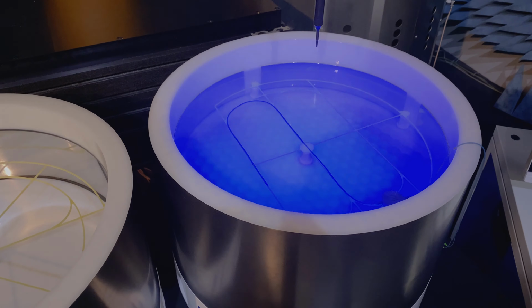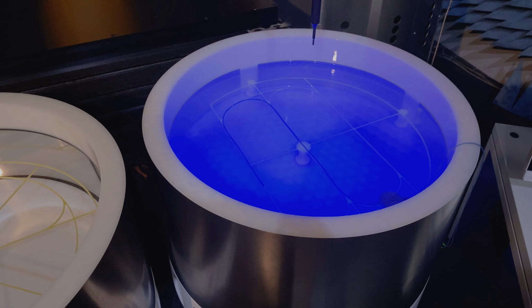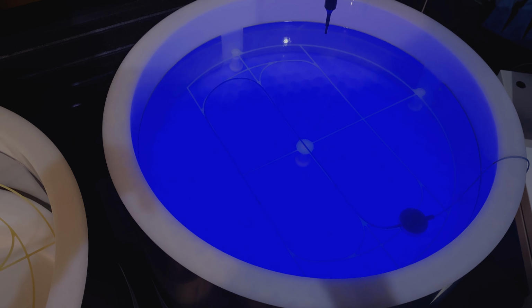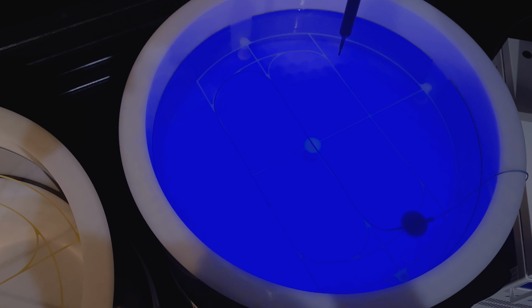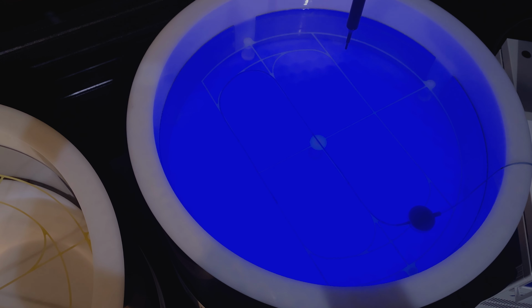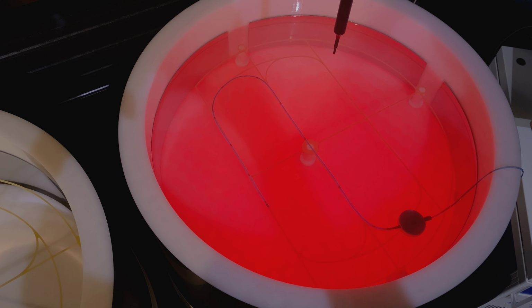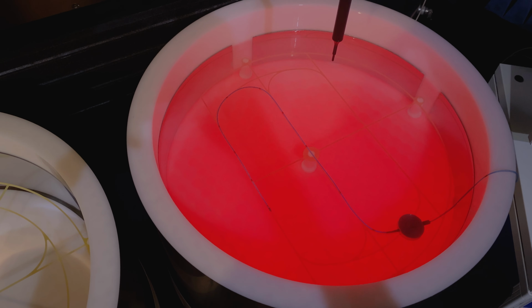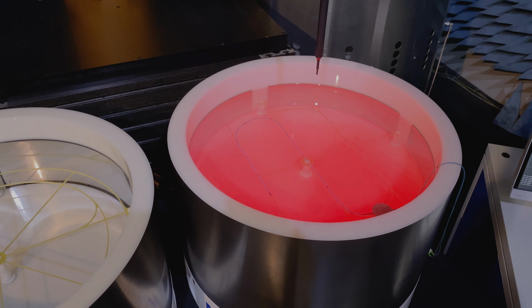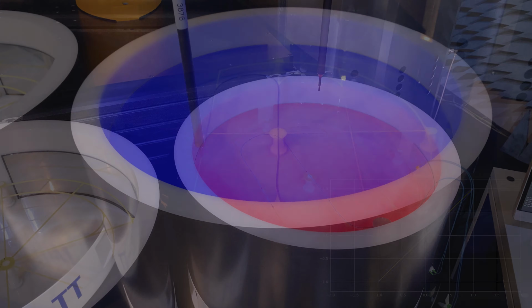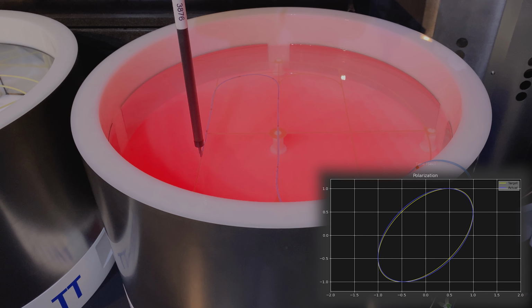Once I turn on the system, the blue light indicates now that the amplifier is activated. Let me choose a circular polarization and start the exposure. As you can see, once the exposure is started, the light turns red. Now I can use DASY to measure the power around the tip, or a temperature probe to measure the heating. Here we'll capture the point-specific absorption rate, SAR, at 20 different polarizations in real time. These could also be temperature or induced voltage measurements.